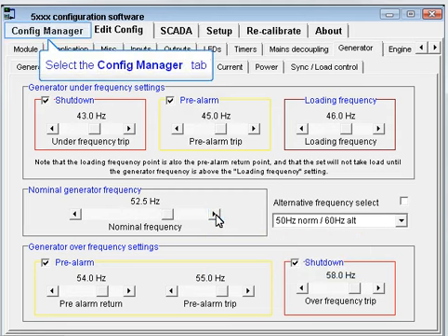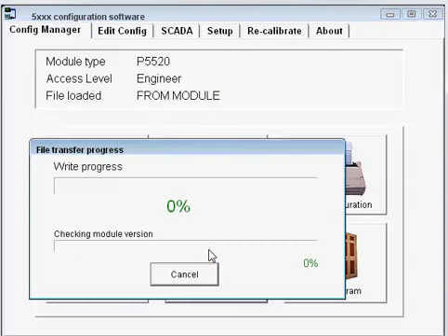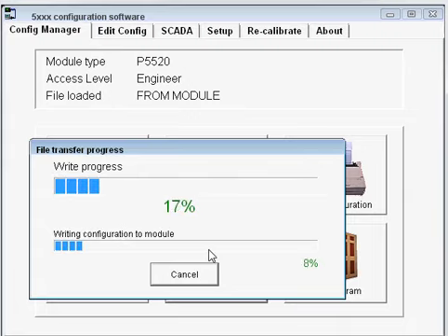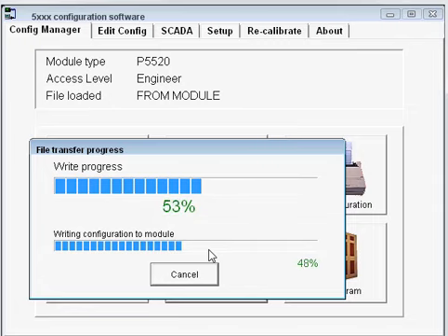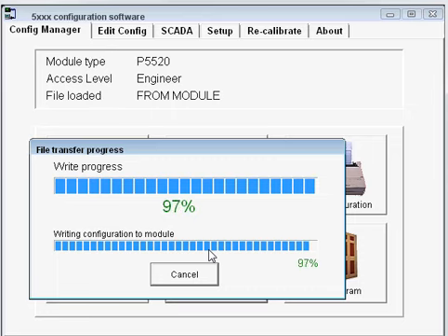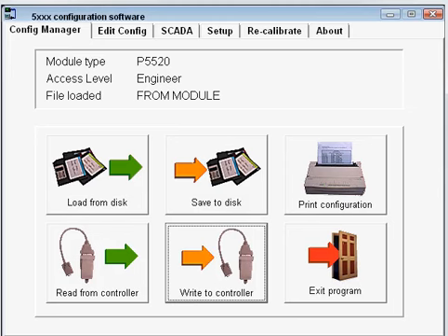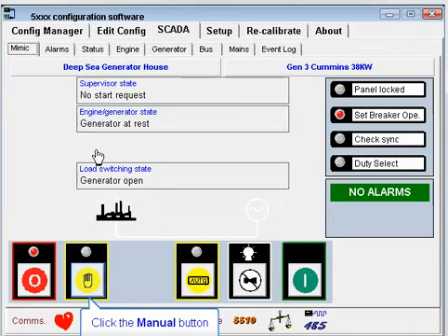Now return to the config manager page to write the configuration to the controller, instructing the set to run at the new frequency. Use the SCADA Mimic page to start the engine, by placing the module into manual mode and pressing the start button.